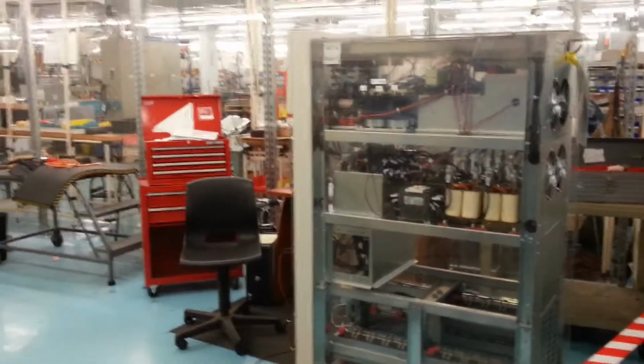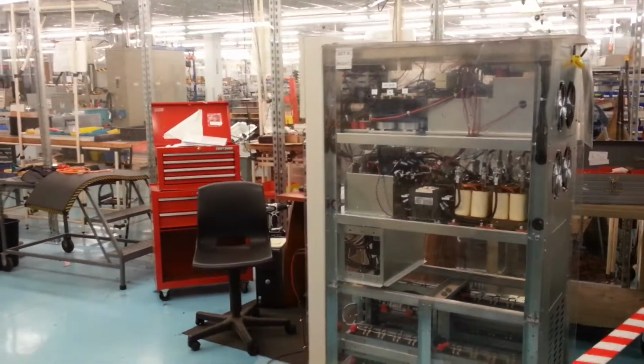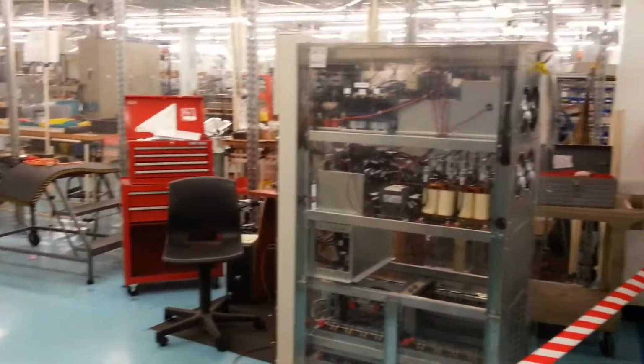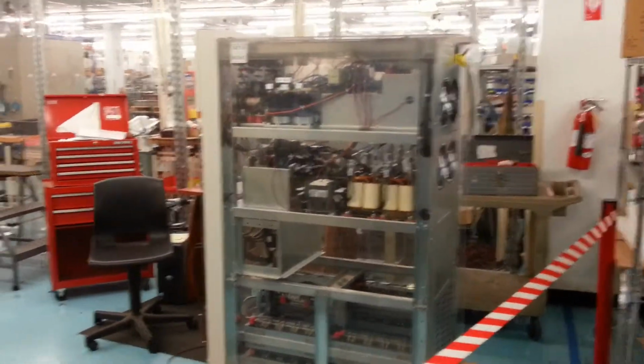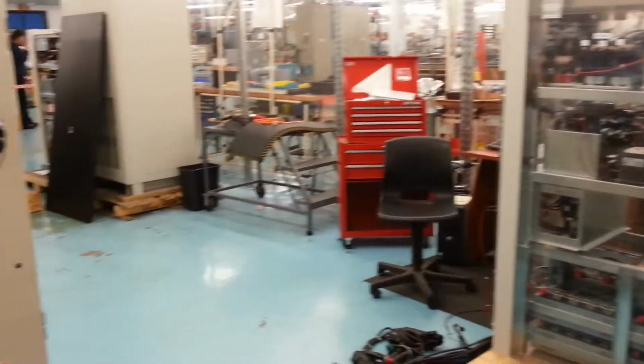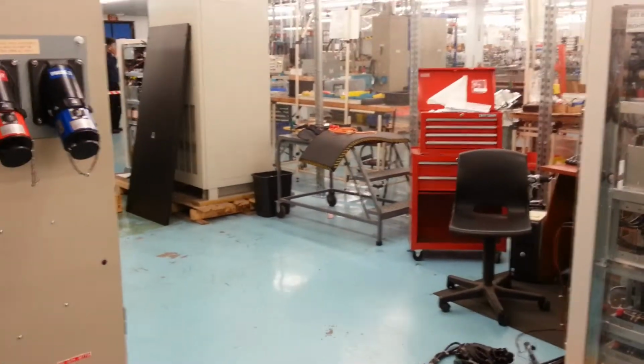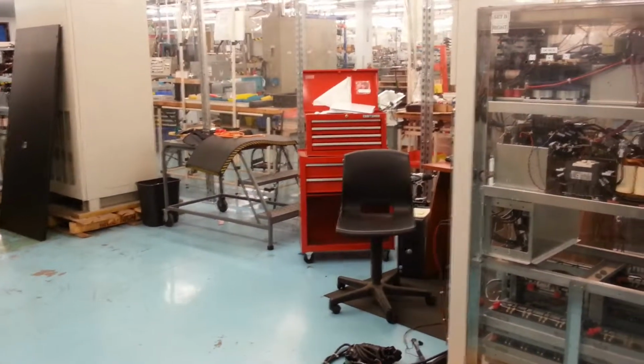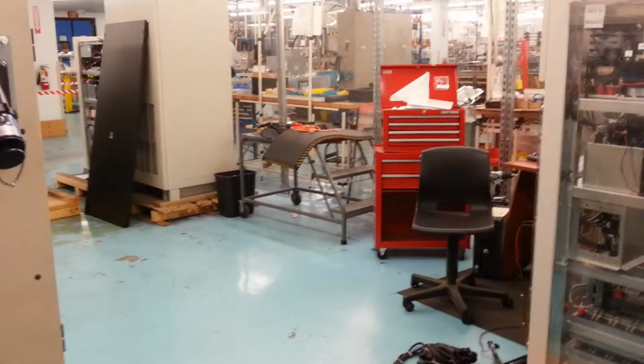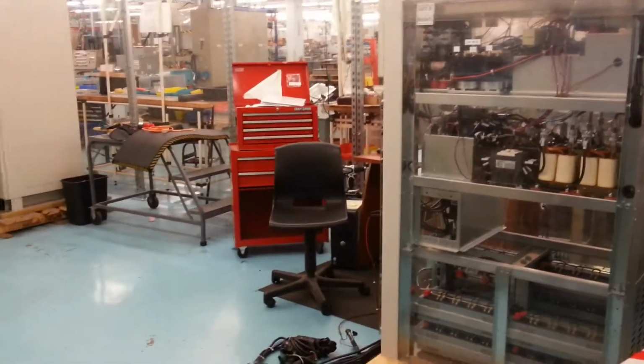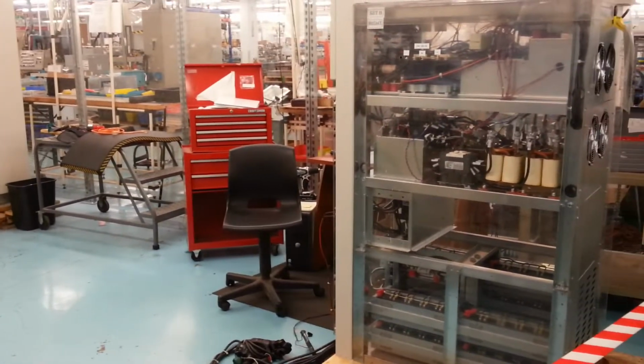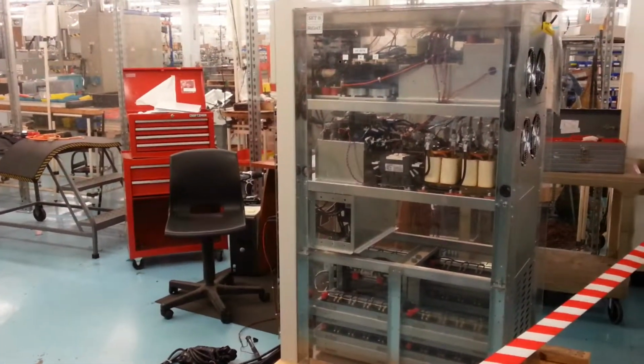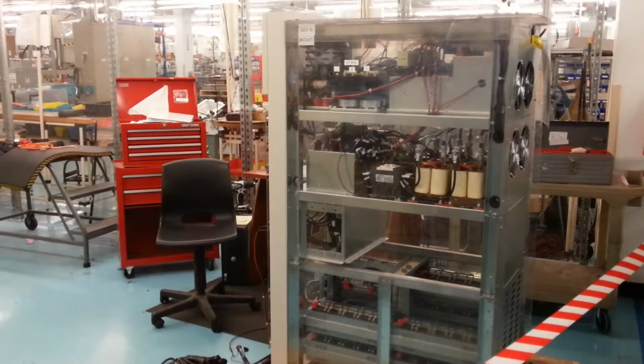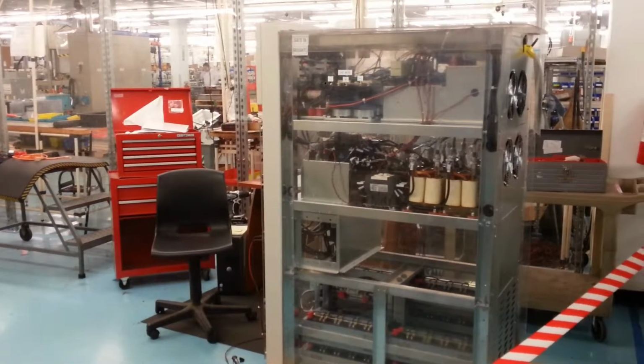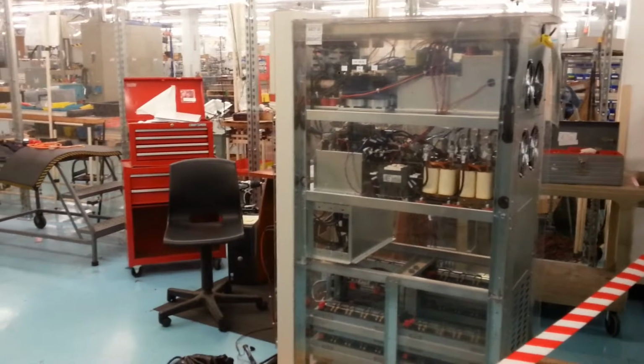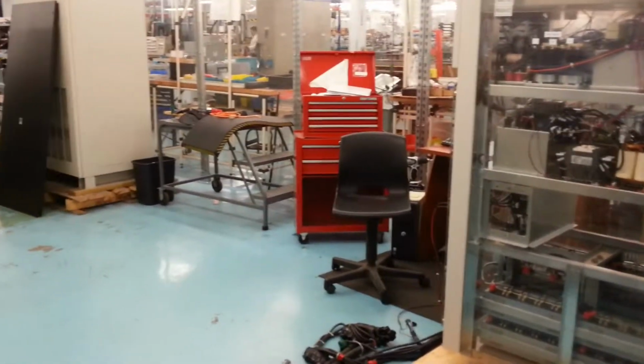Would the generator backup plug into this, or? Well, you can on the input of the unit, not into the UPS itself. Normally, that's a lot of times why UPSs and flywheels are used. A lot of times, customers will buy battery cabinets or flywheels. What they're doing is they're giving their IT guys or their building maintenance supervisor, whoever, enough time to say, hey, we've had a power failure. Outside, everything's dark. We're still running. Which then gives the generator enough time to power up, synchronize, get the frequency right, switch online.